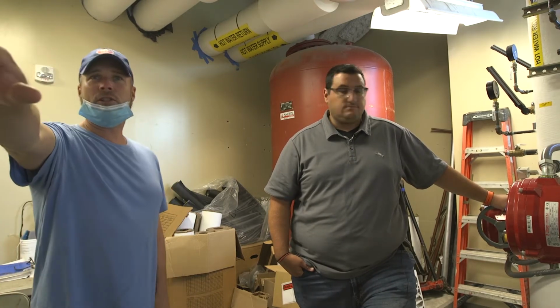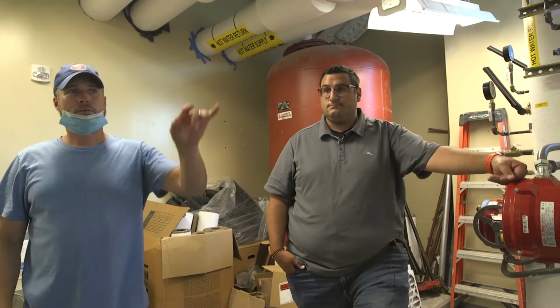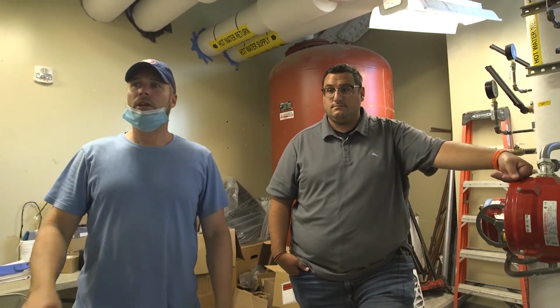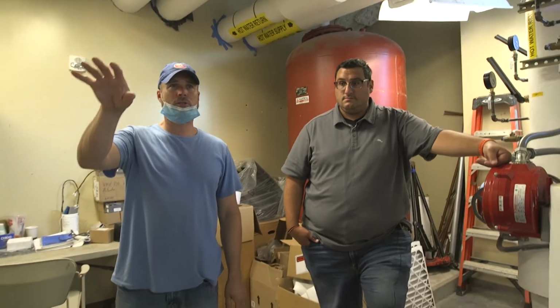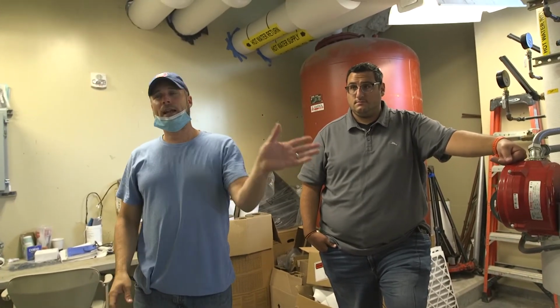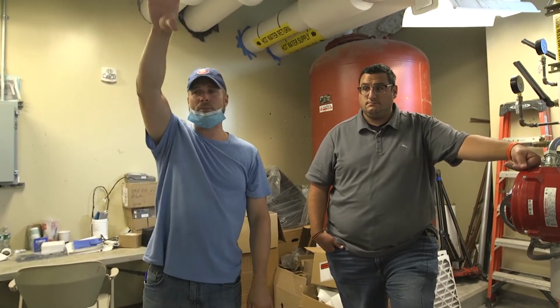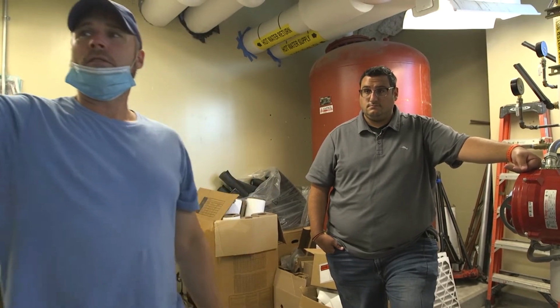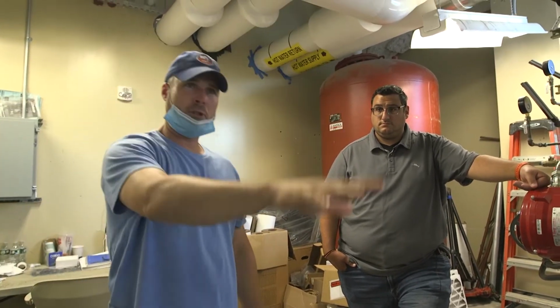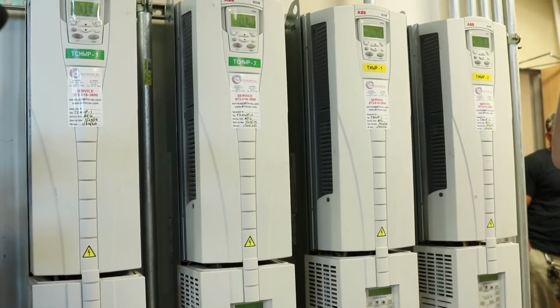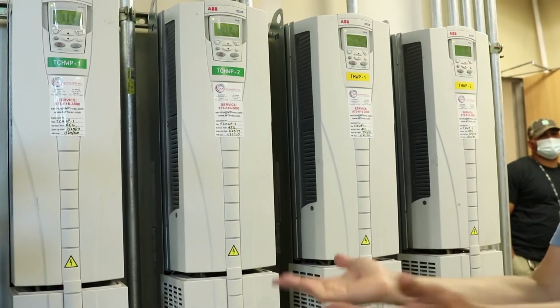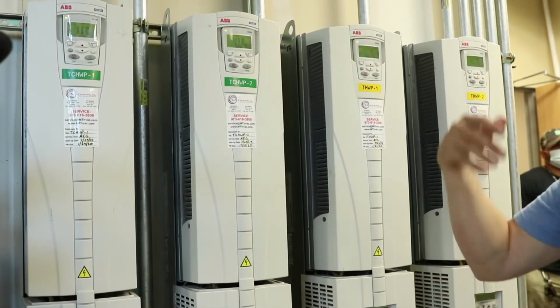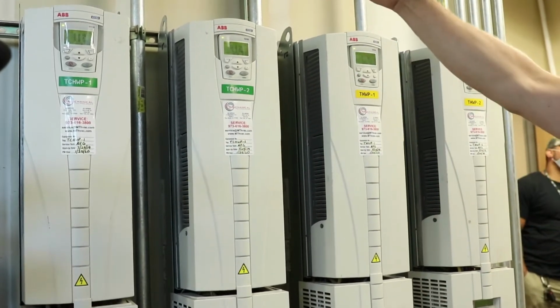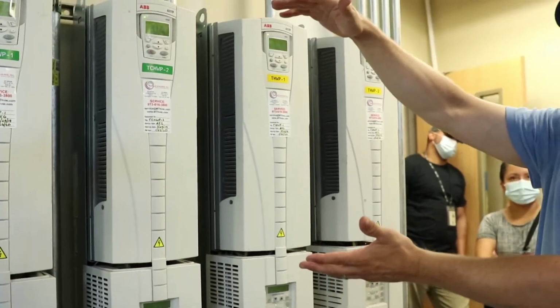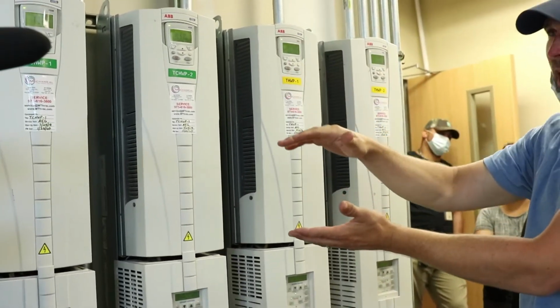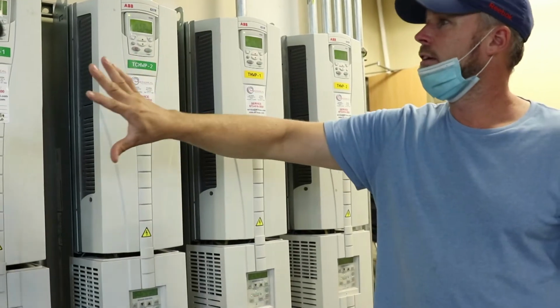Right. These are your VFDs for those pumps. They're all controlling off of differential pressure set points that have the pressure transmitters downstream of the system. So this is what's going to modulate your pump speeds up and down. As devices are opening up and pressure is decreasing in the system, the pumps are modulating higher to deliver more water. As the pressure starts to rise, the pumps start to slow down to maintain your differential pressure set point.